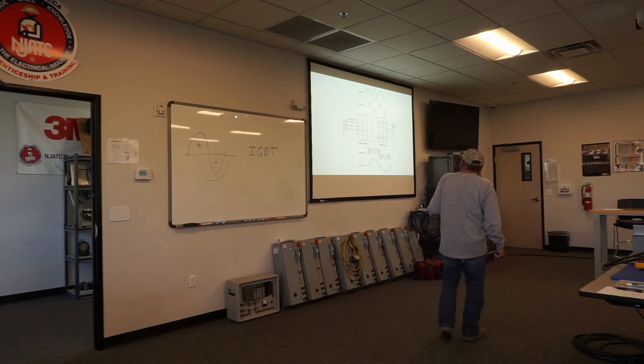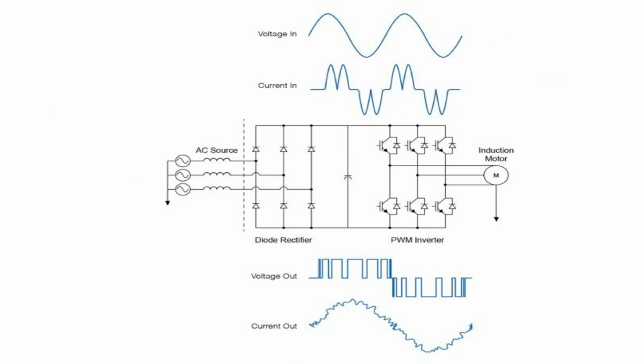So the output now, we hit the DC section, and the IGBT is switching, and as you can see, an IGBT basically has a very short on, and it starts to develop this component of the sine wave. And then you got a little bit larger on, so the sine wave gets larger. And as this sine wave gets larger and larger, this AC component begins to look like a sine wave. Then on the other side it gets smaller, and therefore it drops down. Smaller and smaller, finally we cross the zero line, and now the negative IGBT starts its action. 10,000 times these guys are switching.